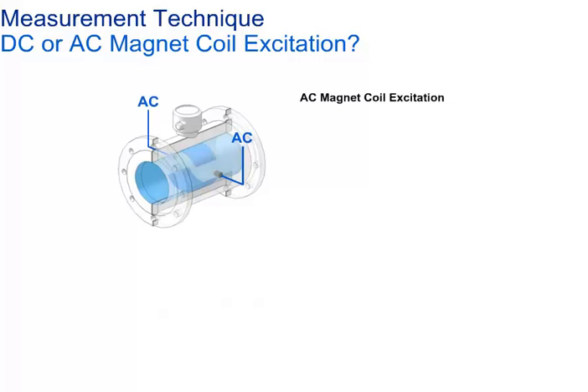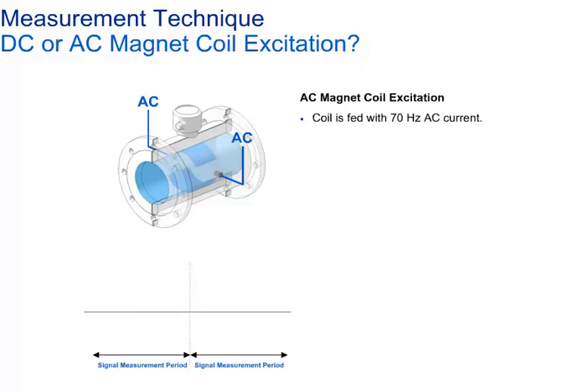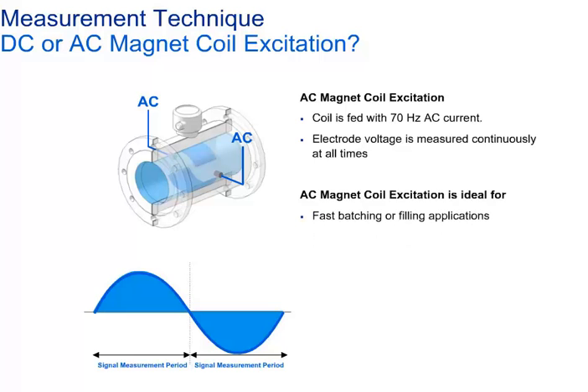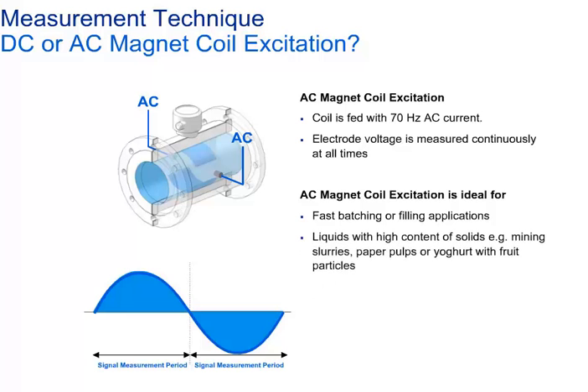The AC field excitation operates at a much higher excitation frequency than the pulsed DC field. The flow signal is integrated continuously. As a result of the higher excitation frequency, noise signals, e.g. due to multiphase fluids, are minimized. This excitation provides a faster response time of the flow meter system. Therefore, it is the preferred version for especially short batch cycles in fill applications. It is most applicable for fluids with high content of solids, two-phase liquids, liquids with low conductivity, or pulsating flows produced by piston pumps.